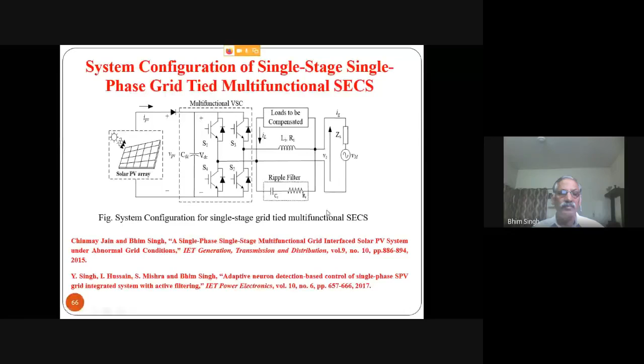The control works by sensing PV voltage and PV current, and doing MPPT from the power, getting the reference DC link voltage for MPPT for the solar. We get a feedback voltage, which will certainly have a second harmonic due to the nature of the single phase system. The DC link will have some second harmonic regardless of the capacitor value used, though the value may reduce it. So you pass it through a low pass filter, with a cutoff frequency chosen because the ripple will be about 100 hertz for a 50 hertz supply, so you keep the cutoff frequency around 25 hertz. Then you get only the DC component, forming the reference for MPPT, using a proportional integral controller responsible for MPPT. This is considered typically as a kind of loss - if solar generation is not there, this becomes a loss of the converter which should come from the grid.